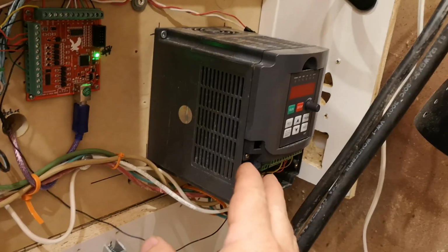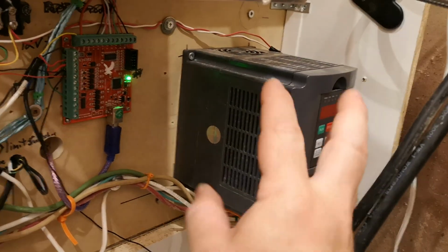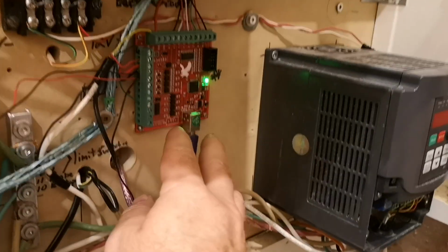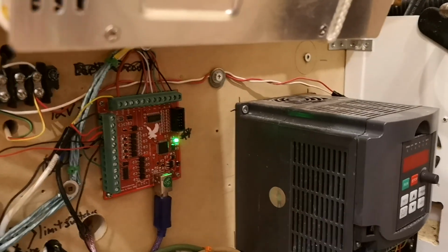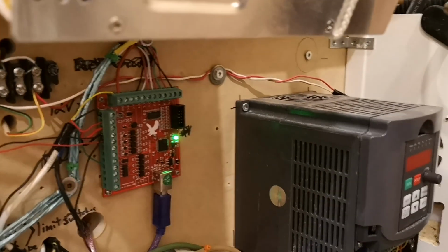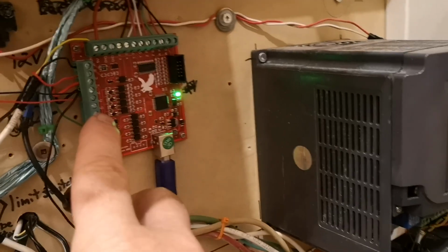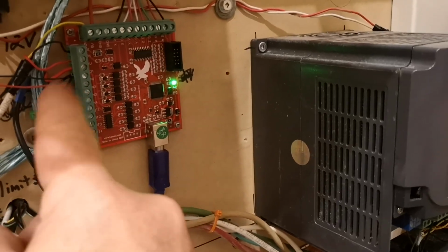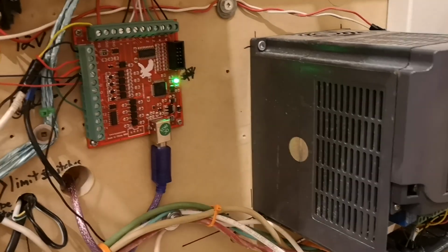It's a 10 volt reference voltage. So it's coming out of here, it's going up here, and it's telling this board, this is what the VFD sees as 10 volts. And then it does its thing and sends out the proper response.